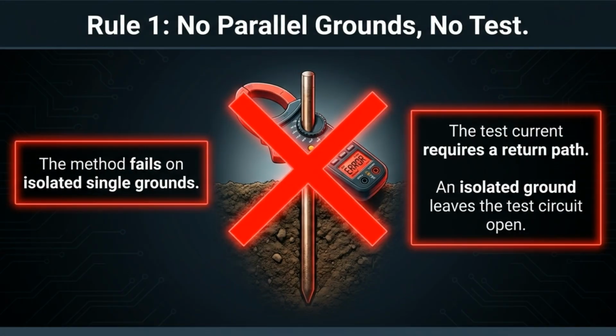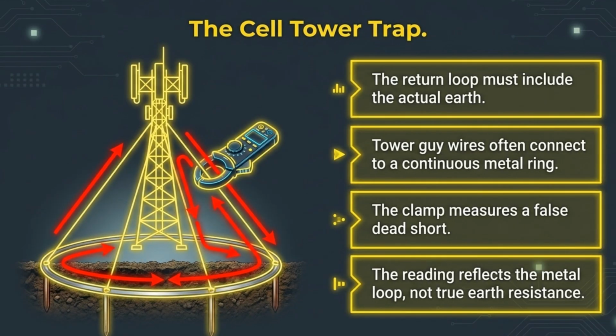However, there is a key rule. No parallel grounds means no test. The method will fail on isolated single grounds because the test circuit requires a return path to function. Be aware of the "cell tower trap." If the return loop doesn't include the earth, for example, if guy wires connect to a continuous metal ring, the clamp will measure a false dead short.